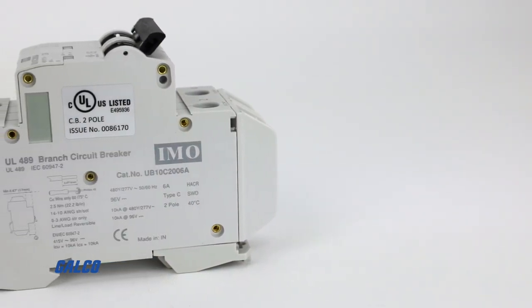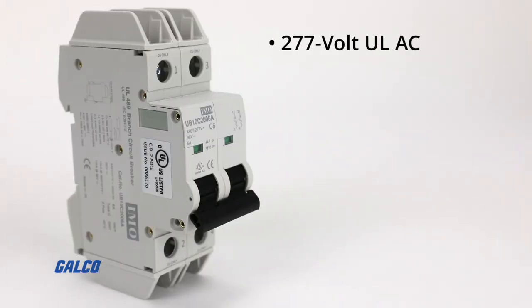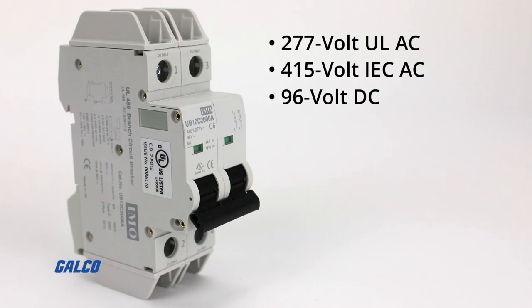The UB-10 series are UL489 listed and are best suited for branch circuit device protection. They provide 277 volt ULAC, 415 volt IECAC, and 96 volt DC service.